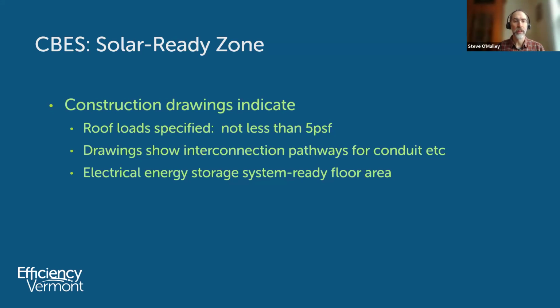And then there's the electrical energy storage system ready floor area. I'd imagine, if thinking of a 3-story building above a parking garage, it's at the parking garage level. The idea is there doesn't have to be energy storage installed at the time of construction, but there has to be space for future energy storage. Whether it's battery, or even potentially hot water if using an air to water heat pump, somewhere that has to be designated in the drawings.